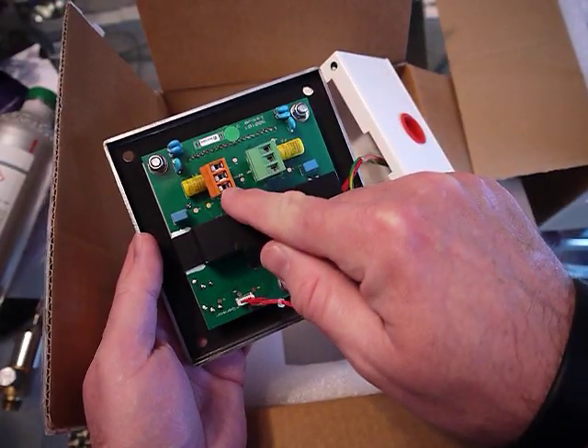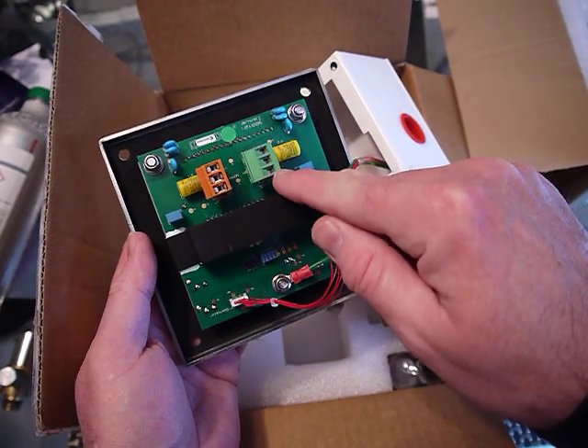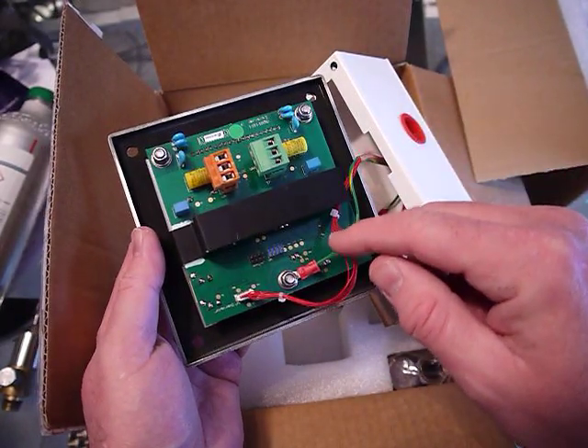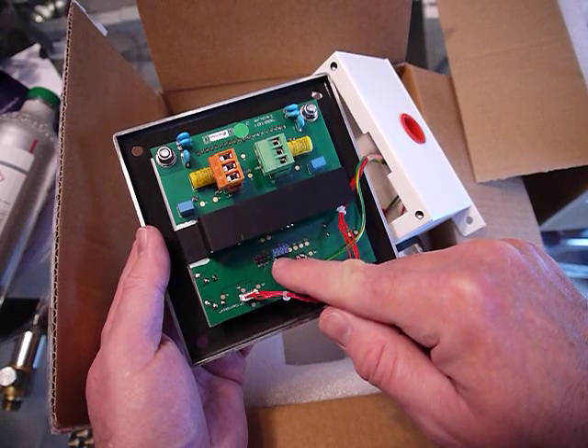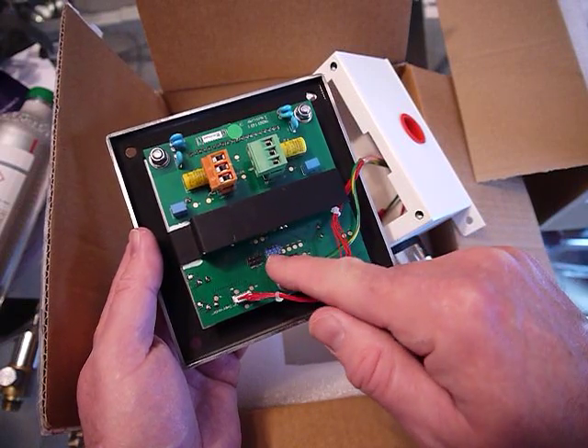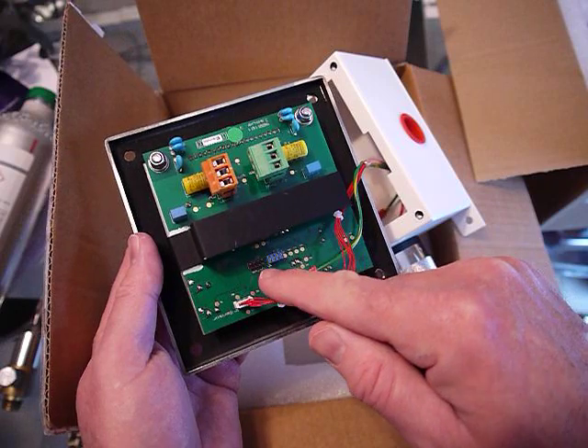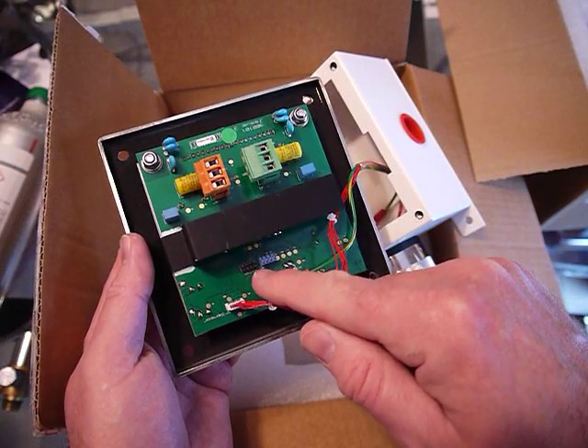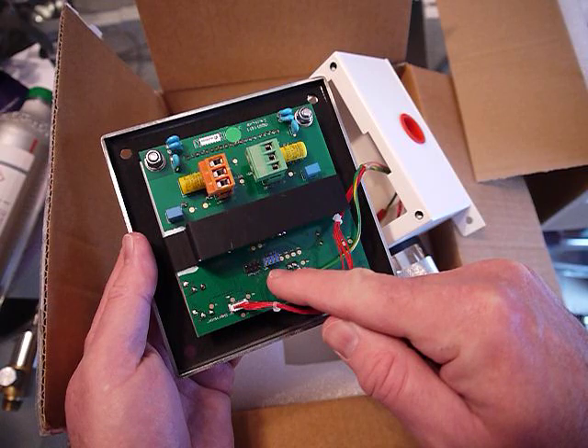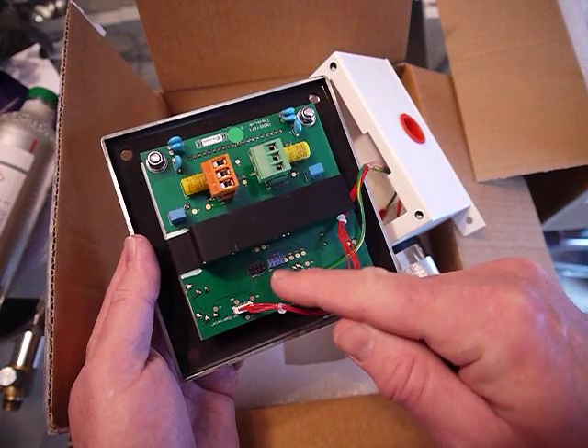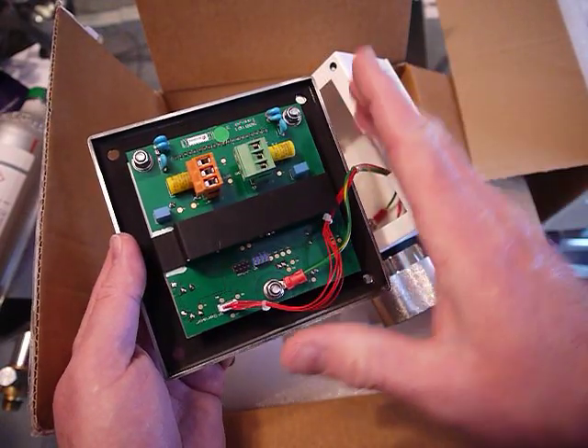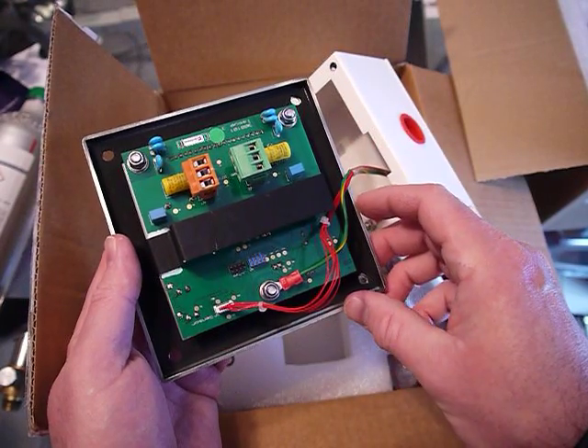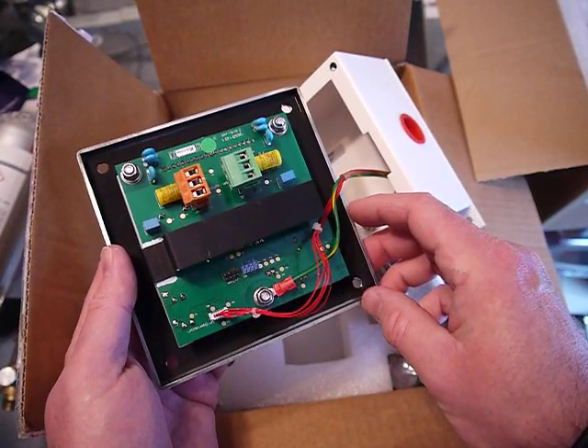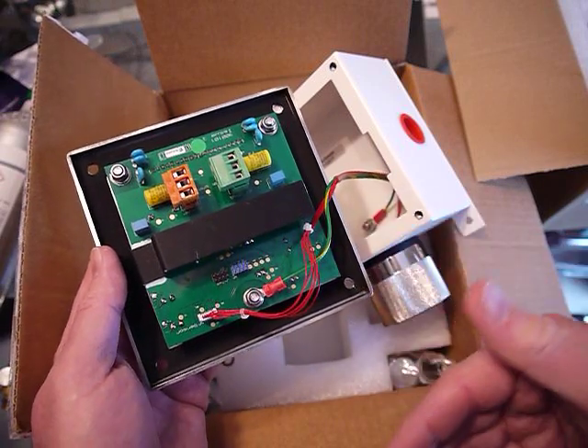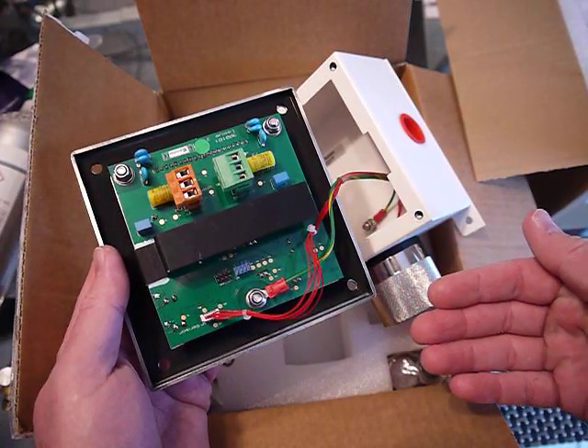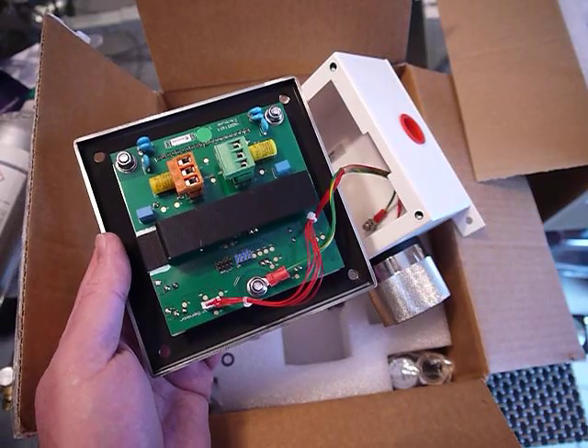power here is a connection. We have 4 to 20 milliamp out. Also, there are these jumpers down here, and depending on how the jumpers are set, that gives you different ranges of the instrument. So I believe from the factory it's set to 0 to 1000, but you could change that range with those jumpers. So this is a very quick overview, and this will be part of a larger playlist of other videos, such as Ion Science. They made a video on calibration and bump testing, changing the lamp and stuff like that, so I won't cover it in this video.